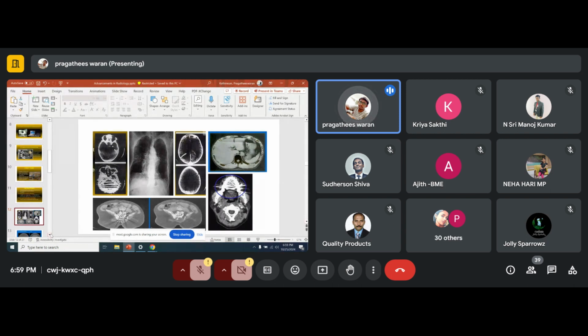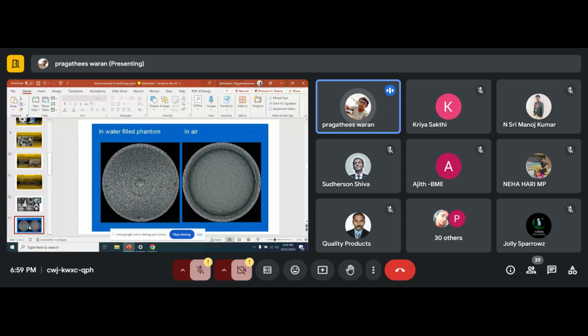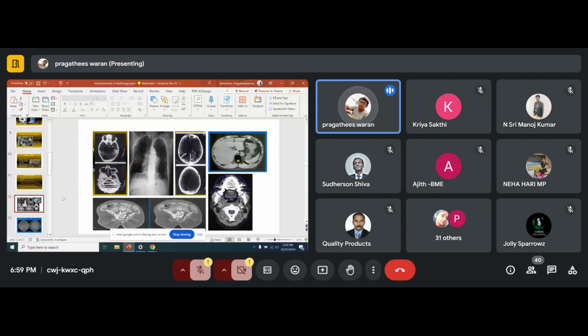So as a service engineer, what we do once a customer logs a complaint, like I am facing this kind of artifacts: first, we used to do a calibration. We have phantoms. A phantom is nothing but a glass filled with some water, and a particular portion will be similar to bone in density, like a PP phantom, a polypropylene phantom. We take a scan with that phantom and check if things are okay, then we start our troubleshooting with the phantom.